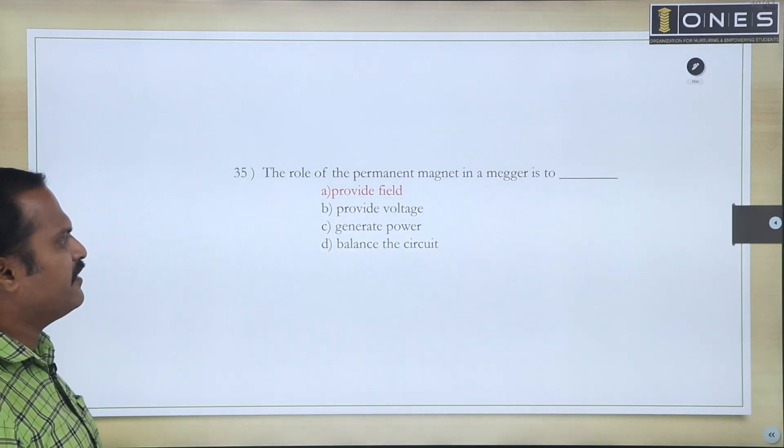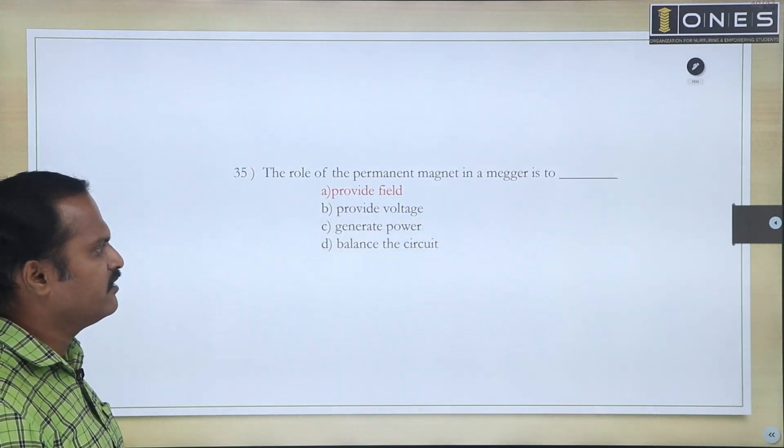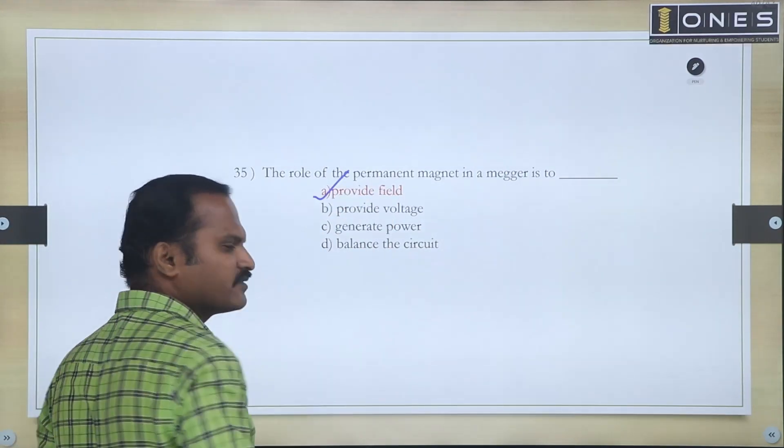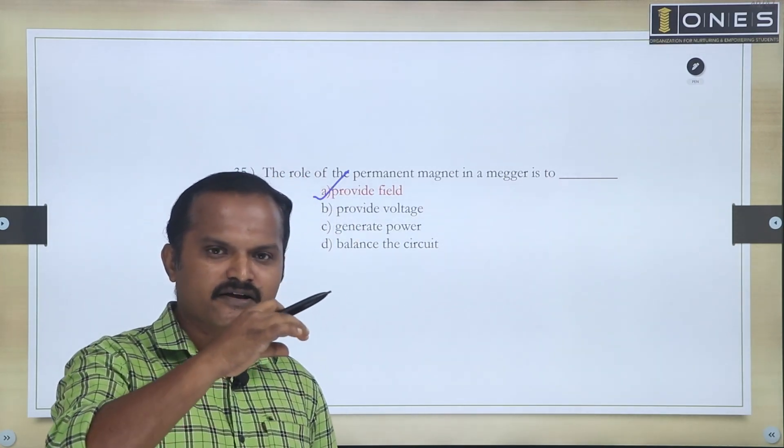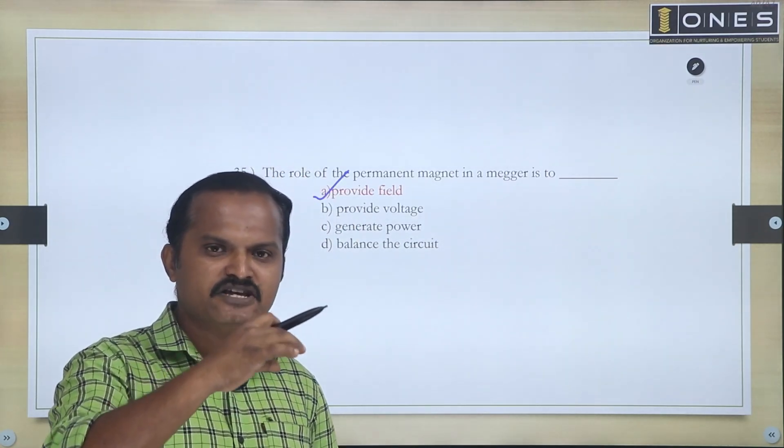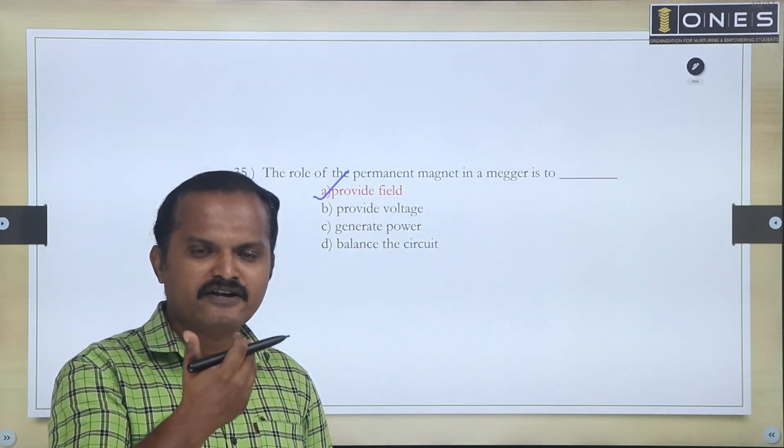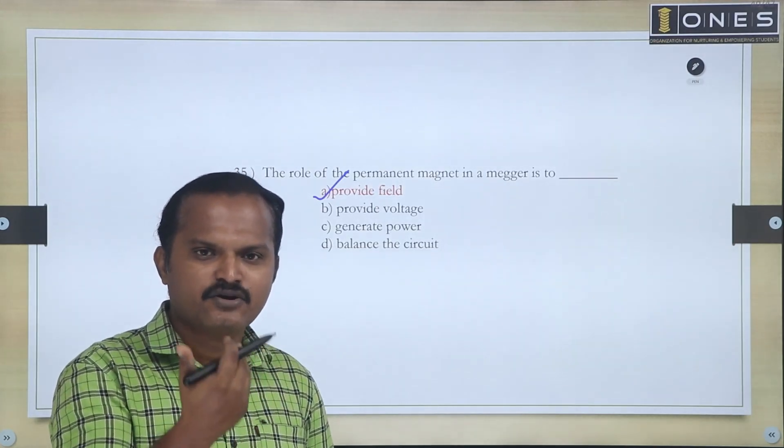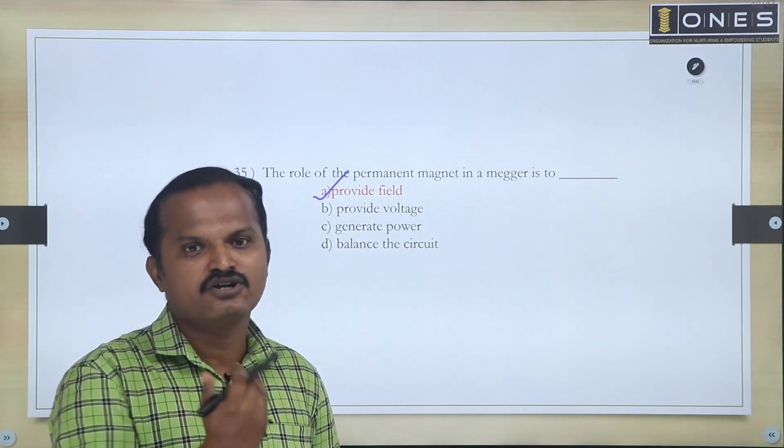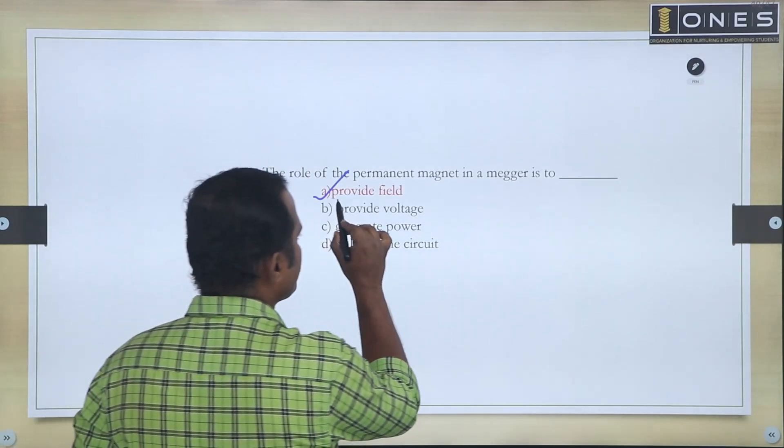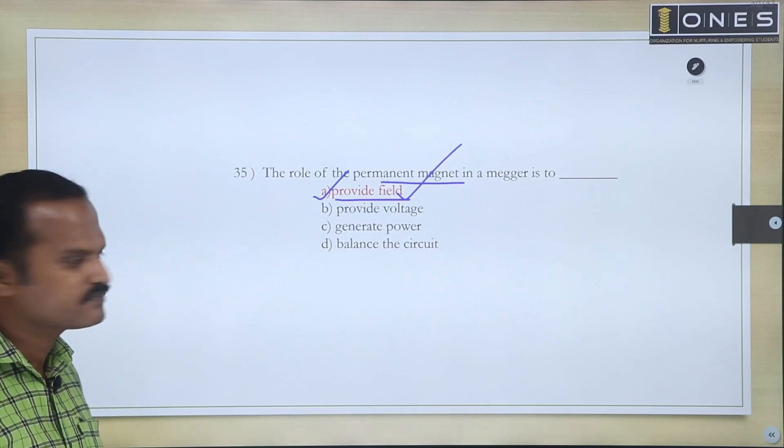Next question: The role of permanent magnet in the Megger. The permanent magnet function is mainly used to provide a field. We have two coils, C1 and C2. The permanent magnet is underneath. When current passes, automatically the coil will act as an electromagnet. The interaction between these two fields causes torque to develop. So the main purpose of your permanent magnet is to provide a field.